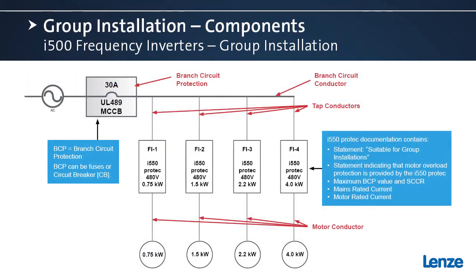Here's an example of a typical group installation using the i500 series protec frequency inverters. A few things I want to highlight on this slide. Starting from the left, you'll see, of course, an AC power source that is, in this example, connected to a 30 amp UL489 marked molded case circuit breaker. That's the branch circuit protective device for the group.